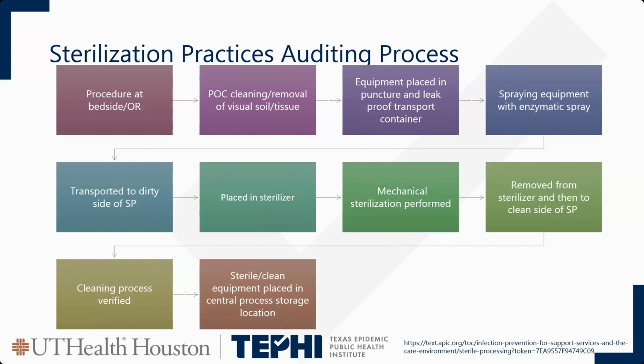So while you're in the case, just like before with high-level disinfection, you're seeing the physical removal of blood, tissue, and soil from that specific device. That is surgical shears, that's stitches, anything that's going into that OR. The physical tissue and blood should be removed either with a surgical sponge or a lint-free cloth. And then it's placed in a leak- and puncture-proof container and sprayed with your enzymatic spray according to that wet time. Then you are going to physically go with that device down to the dirty side of sterile processing. Sterile processing, depending on your facility, should be set up in either two or three different components. You're going to have the dirty side, the clean side, and the sterile side.